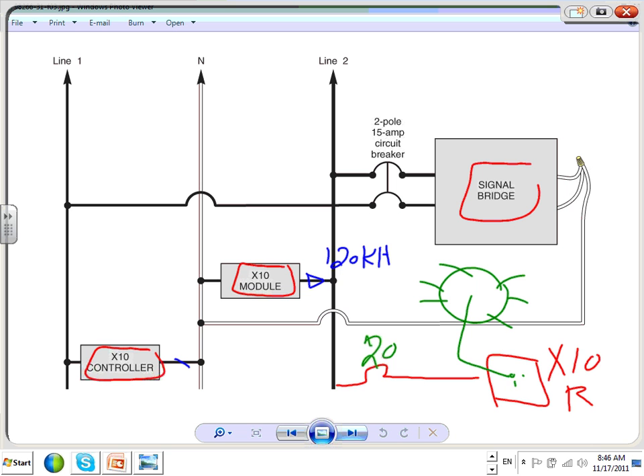So look at this. This signal is coming in here all the way through the circuit breaker, all the way to the equipment. Now, when this X10 receiver gets it, it has a device that can take that 120 kilohertz signal and act upon it, make things happen. Basically, turn it on and off or dim it. But look, see how the communication happened? There are no extra wires, right on the power lines. Does that make sense? That's a very powerful concept.